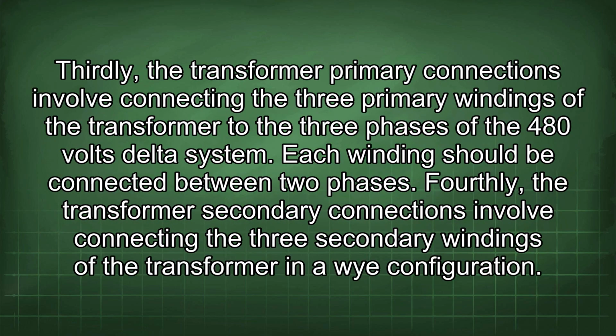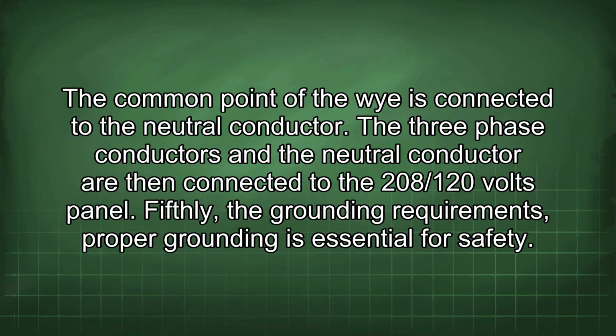Thirdly, the transformer primary connections involve connecting the three primary windings of the transformer to the three phases of the 480 volts delta system. Each winding should be connected between two phases. Fourthly, the transformer secondary connections involve connecting the three secondary windings of the transformer in a Y configuration. The common point of the Y is connected to the neutral conductor.